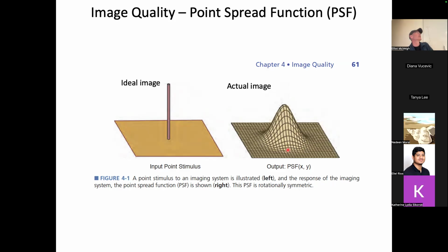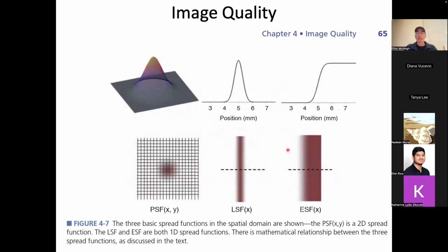Another way of doing it in 3D on a CT scanner is we will take one of those really nice Japanese Pentel pens that are sort of a 0.3 millimeter ballpoint pen. It's the super fine one. And so when you write with it, you get these tiny thin lines. So we'll just break that and take that ballpoint out of the pen and put it on a piece of tape, put it in the scanner on a plastic phantom, just tape it on there, and it'll be a very bright dot. And that dot is 0.3 millimeters, which is below the resolution of a CT scanner. So it will create this Gaussian blob, right? So that's how you do it.